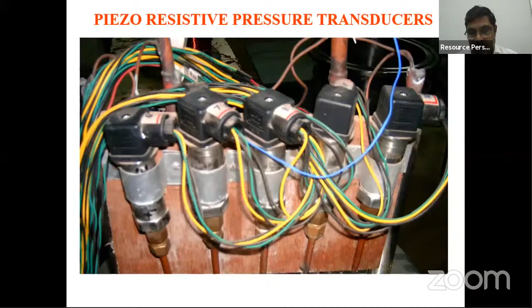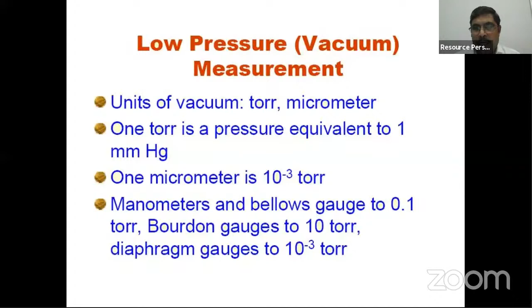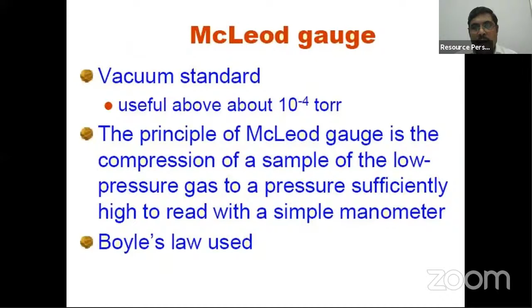Now let us move to the low pressure measurement, the McLeod gauge. Most of you have heard about it. The McLeod gauge is the standard for vacuum pressure measurement. The unit of vacuum pressure is torr. 1 torr is equal to 1 mm of Hg.